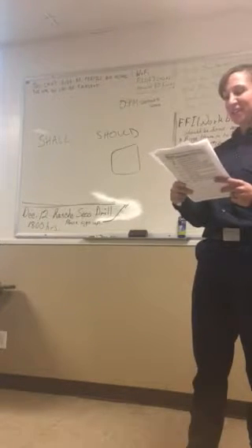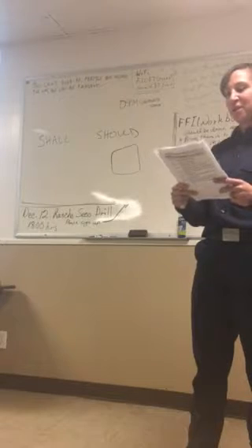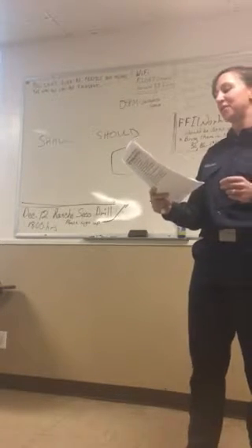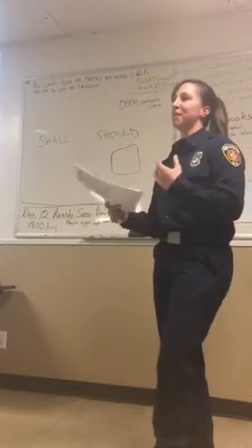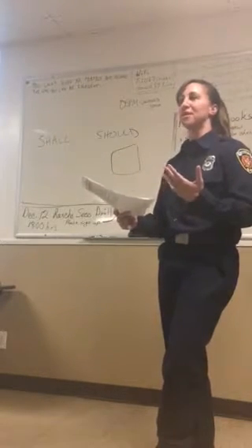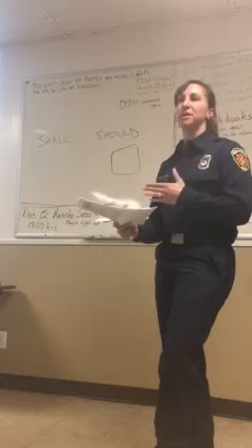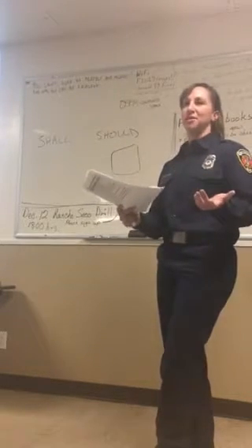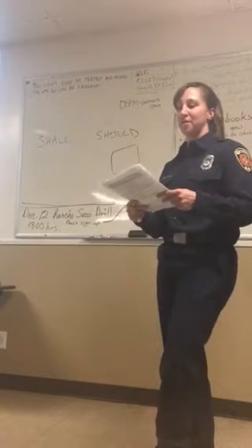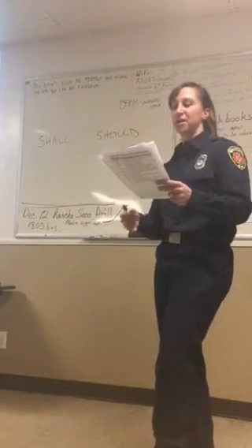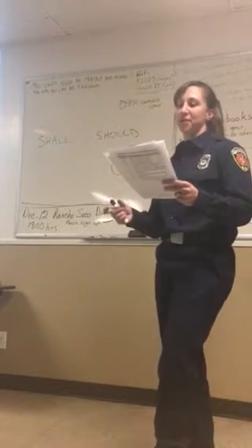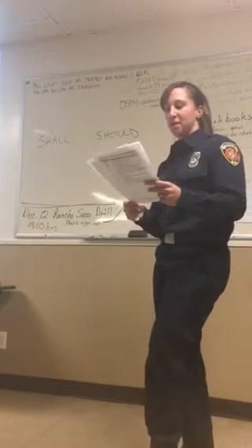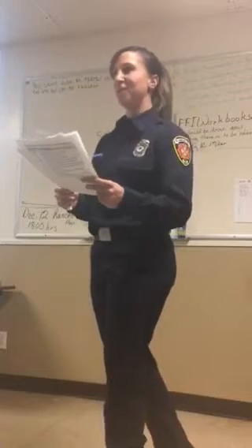So some guidelines that you have to follow. When you go out onto a scene, you want to make sure that you check the oxygen level first. Based upon calibration, if you test a toxic gas or something out of order or sequence first, it can throw off the calibration on the instrument itself. So you want to follow your manufacturer's guidelines. But you want to test the oxygen first, your flammable or combustible levels, and then next you want to test your toxics. Do you guys have any questions?